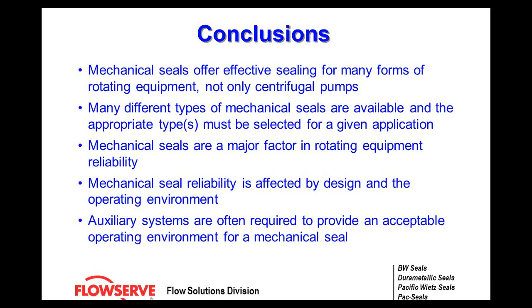Mechanical seal reliability is affected by design and operational environment. Auxiliary systems are often required to provide an acceptable operating environment for a mechanical seal. In dual seal systems requiring auxiliary systems, sometimes pump applications cannot use a sealless pump design — for large pumps, you have to have a mechanical seal. In those systems you want a barrier fluid that acts as a buffer and collection area so that in case of failure, it will not spill out into the environment.